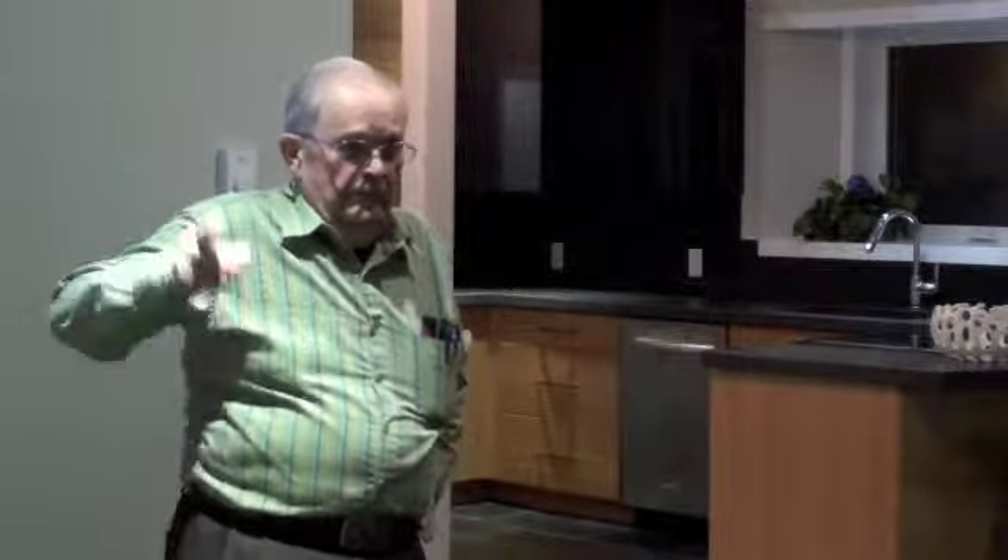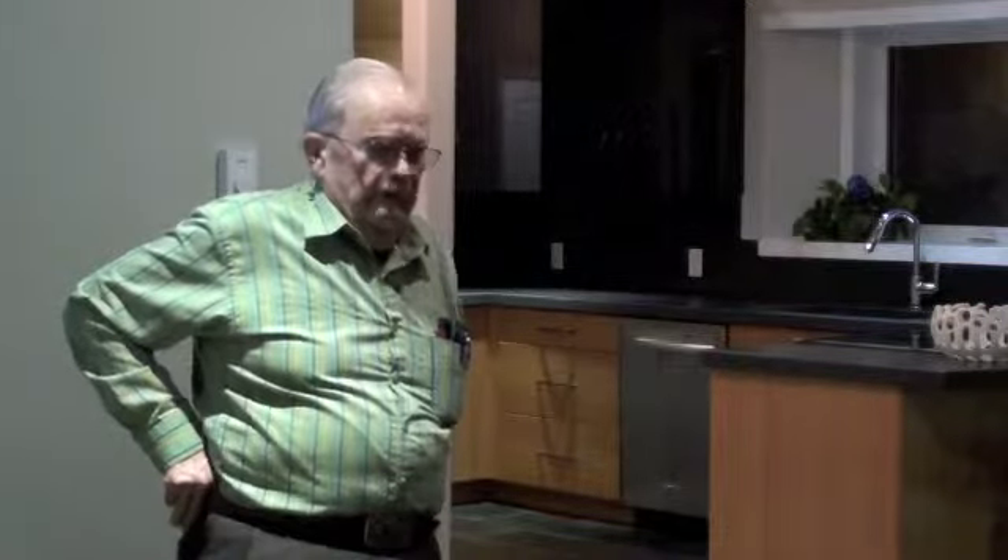We've got a 2,100 square foot house in Humboldt that was heated with a 5 kilowatt electric boiler. We put in 15, then dropped it down to 5 kilowatts. We had to help him because he had it set too hot — he was opening windows. We changed his control settings down using outdoor reset: at minus 35 outdoor temperature, the boiler water temperature going into his floor was only plus 31°C — several degrees cool to the skin — and that was all he needed. Otherwise he was too hot all the time because his house was working so well.